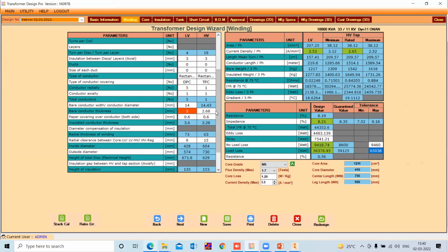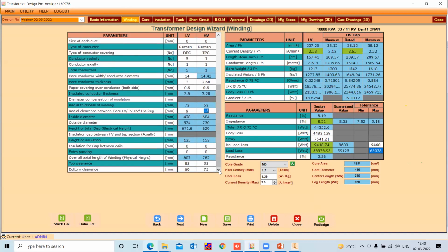Same for the HV side. You can also change the conductor thickness, radial clearances from core to LV and LV to HV. Then the extra packing option is available. Then top and bottom clearances are available to change.